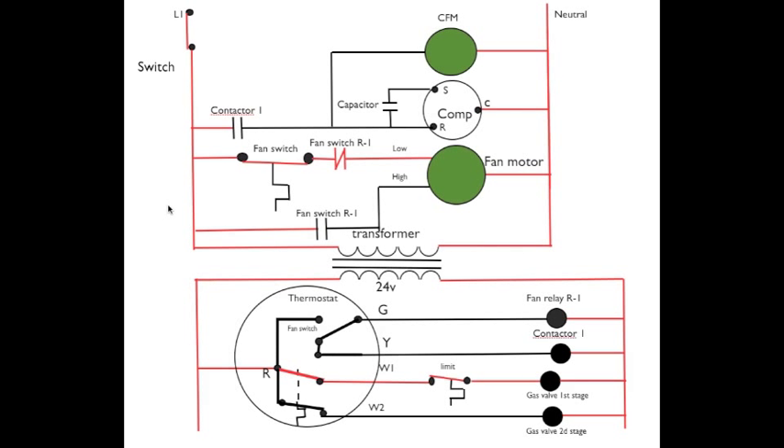Okay, here we have a call for first stage heat. Power passes through R, through the closed thermostat, out W1 — W1 of course is first stage — through the closed limit to energize the gas valve in low fire. Up here in the high voltage, the fan switch closes as the heat exchanger warms. Power then passes through the fan switch relay to energize the fan motor in low speed.